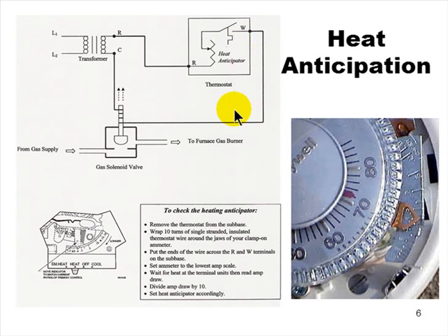Once you've done that, let's say your amp probe's lowest scale goes from 0 to 6 amps. And you do the 10 turns, okay? Now, when you take the reading, it's going to say, for instance, 4 amps. You're on a 0 to 6 amp scale, and it's going to deflect the 4 amps, three quarters of the way up. What that says is you got a 4 amp draw, but you got to divide it by the 10 turns, which means your amp draw, move the decimal point one place, is actually 0.4. That's why you use 10 turns.